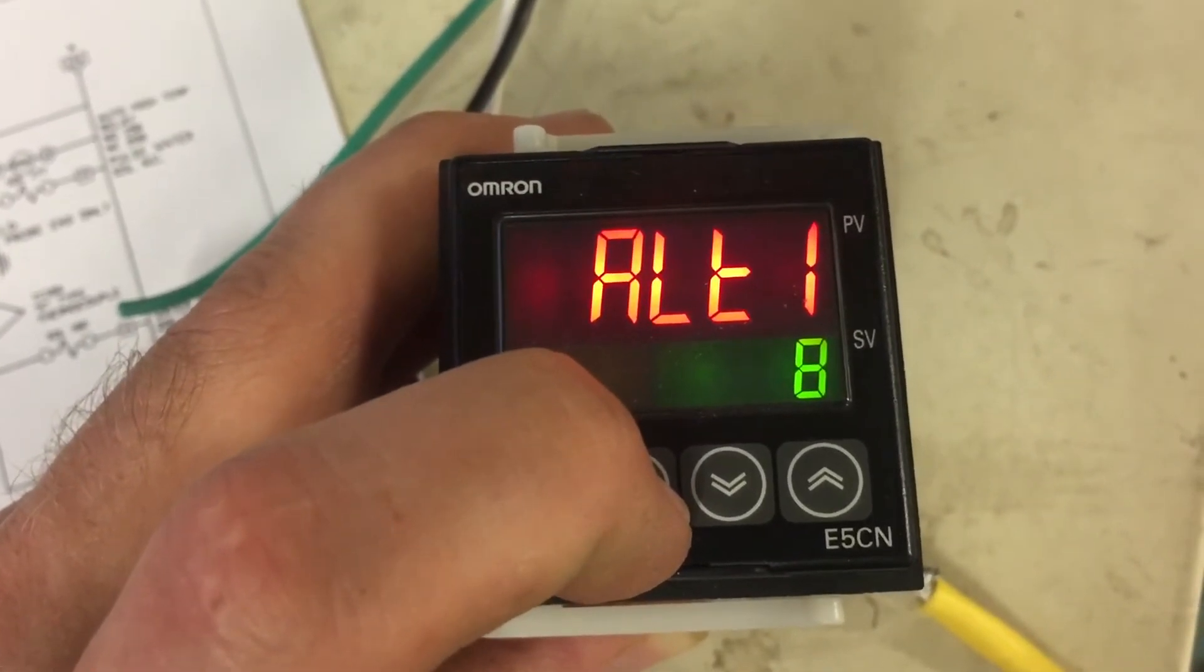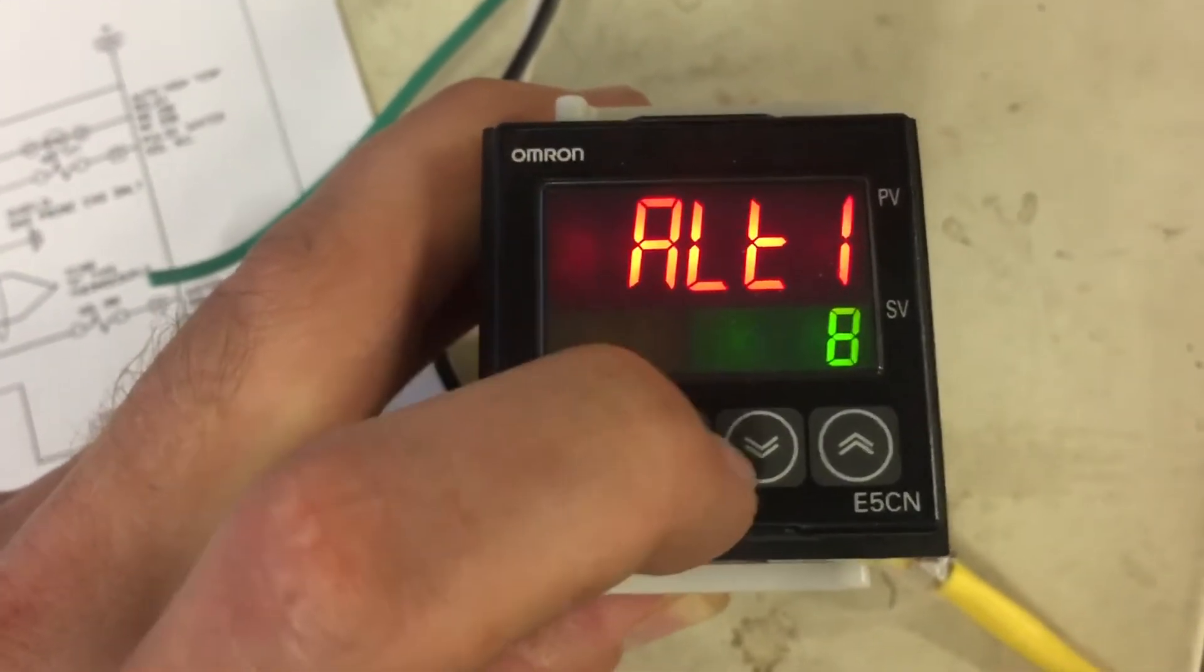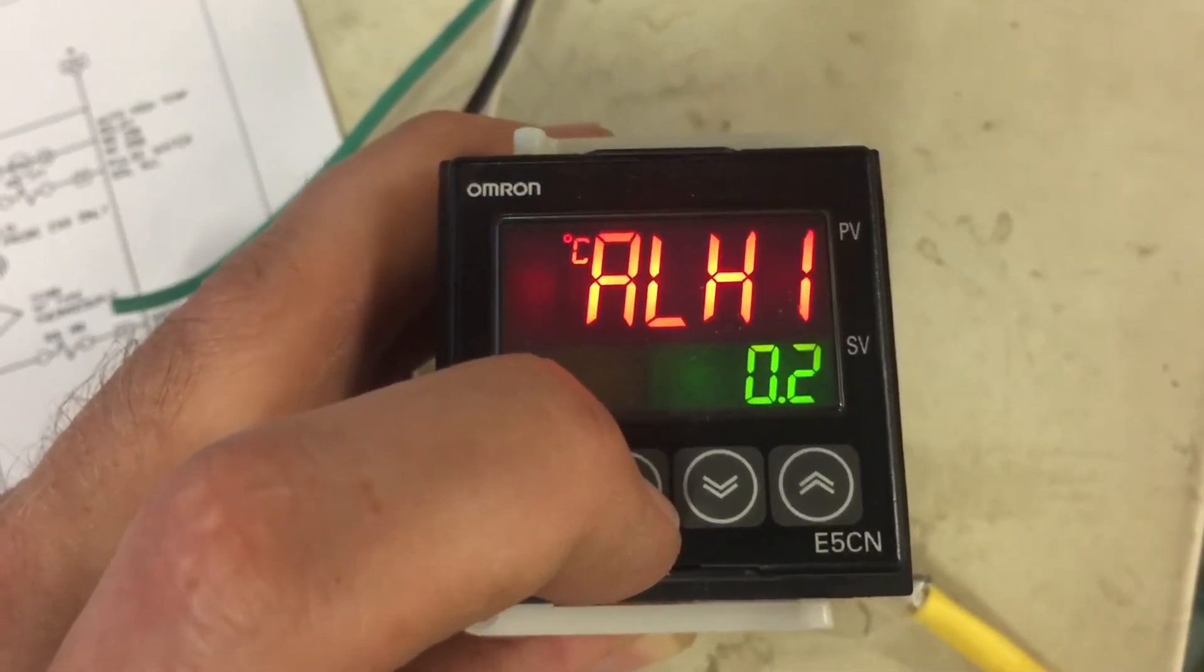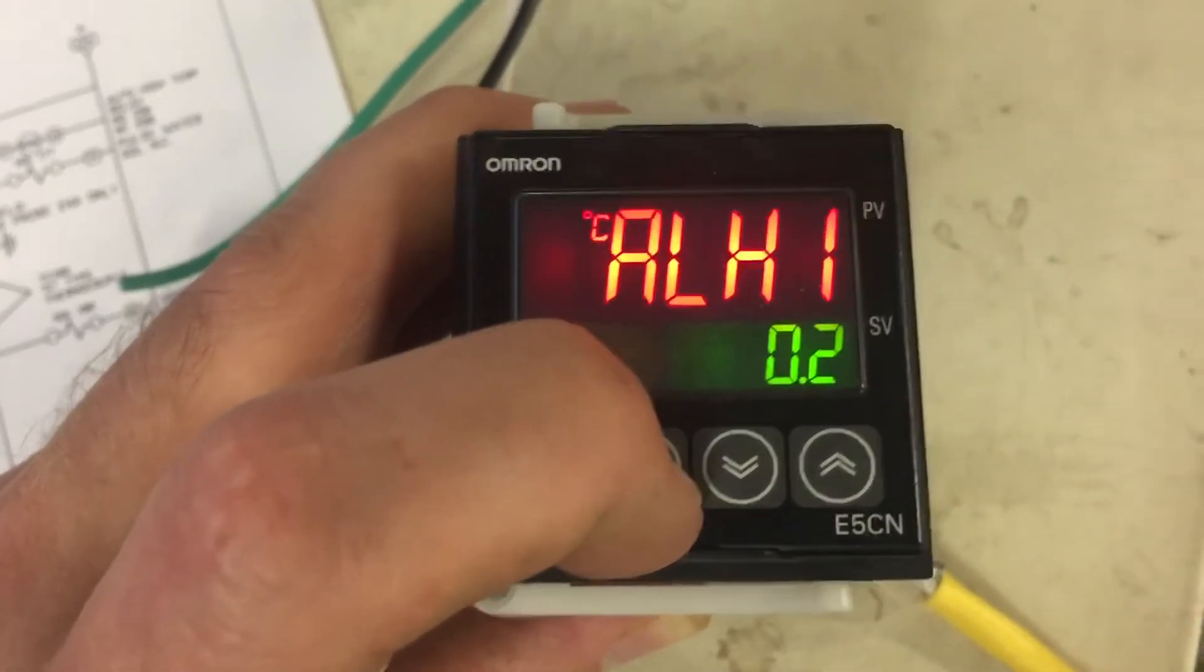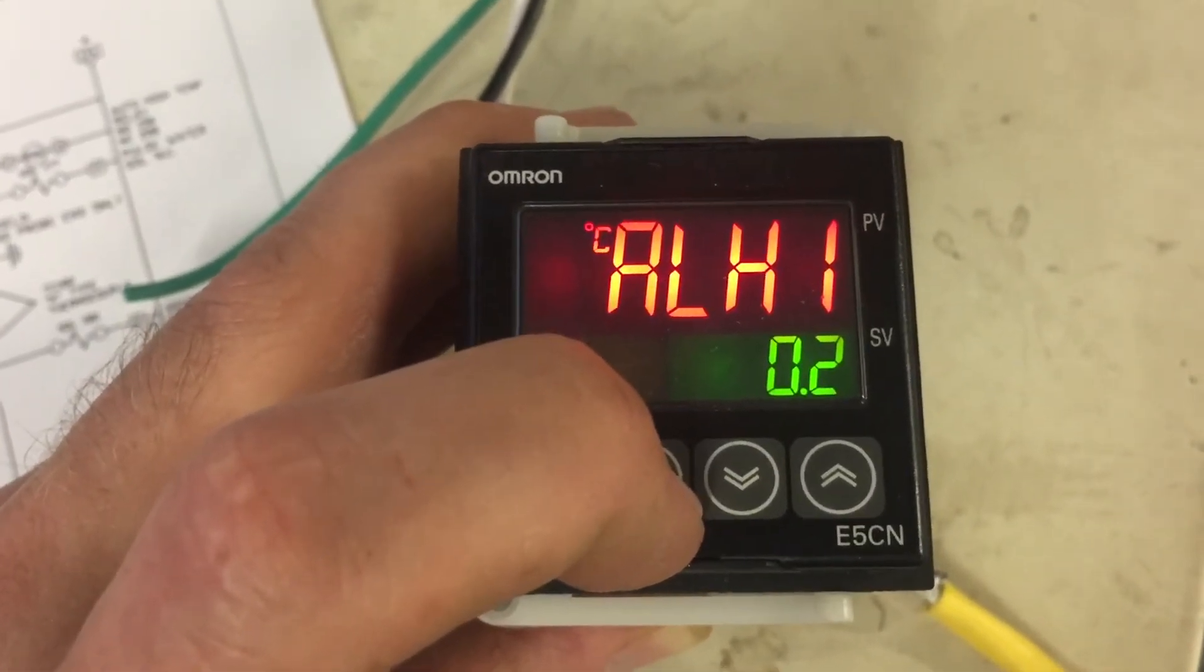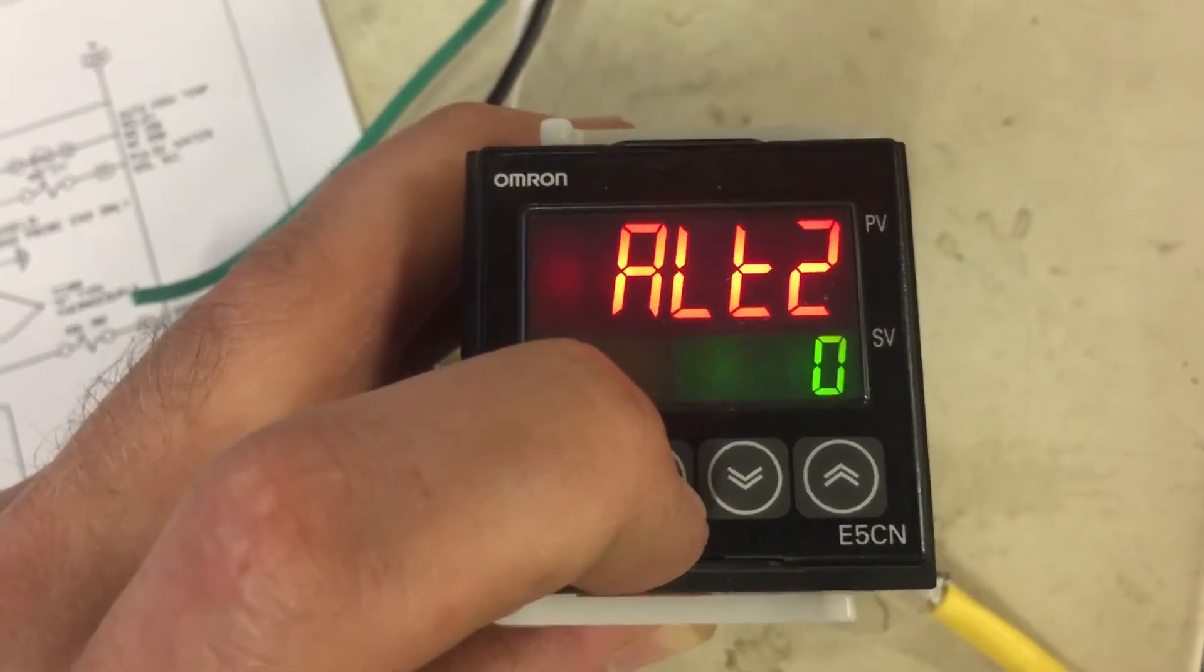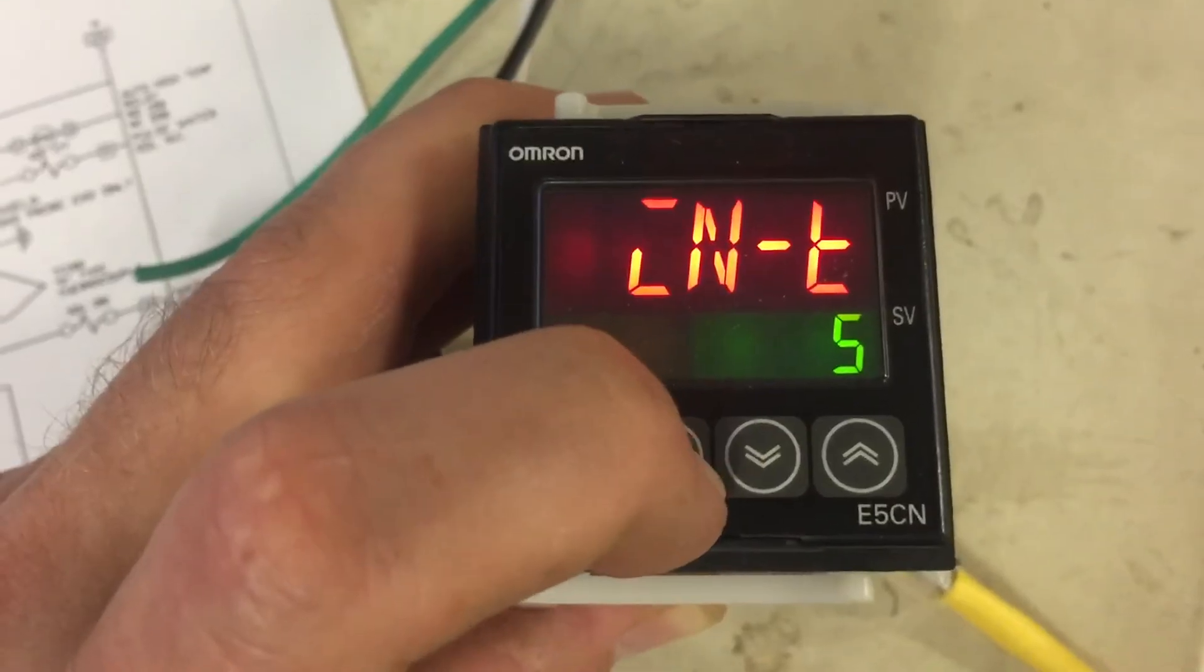ALT1 is going to be 8. This is an absolute value high temperature. And the last value is 0.2 on alarm hysteresis 1. So if it goes within that variable that we're going to now set in the next menu within a 0.2 hysteresis, then the alarm trips. Alarm type 2, we put this as 0 because we don't use it.